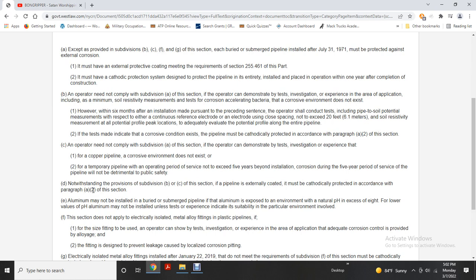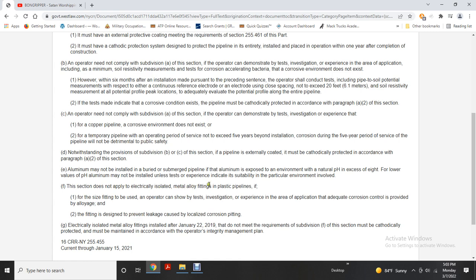Aluminum may not be installed in buried and submerged pipelines if the environmental natural pH is equal to or in excess of eight. Below that pH value, aluminum may be installed unless test experience indicates unsuitability for the particular environment. This section does not apply to electrically isolated metal alloy fittings in plastic pipelines. Electrically isolated metal alloy fittings installed after January 22nd, 2019 must be cathodically protected and maintained according to the operator's management plan.